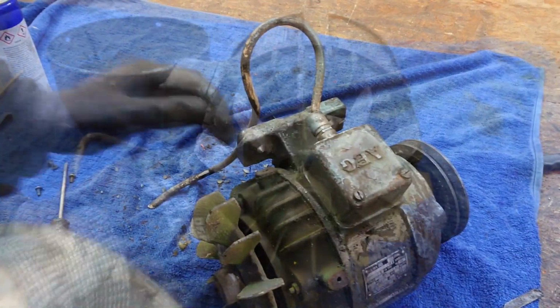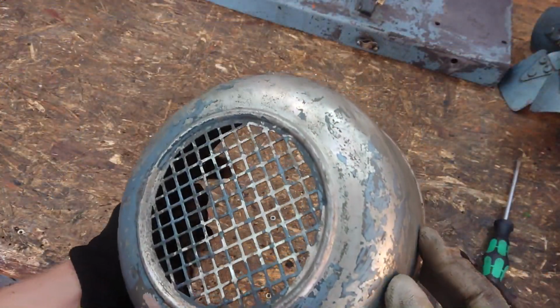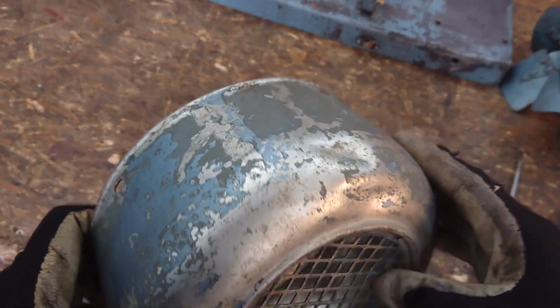Upon detaching the fan guard from the backside of this AEG brand 3-phase induction motor and cleaning the blades, I was able to have a closer look at the dents that caused the sound we heard a minute ago. A self-made punch is used to even that out until the motor can spin freely again.